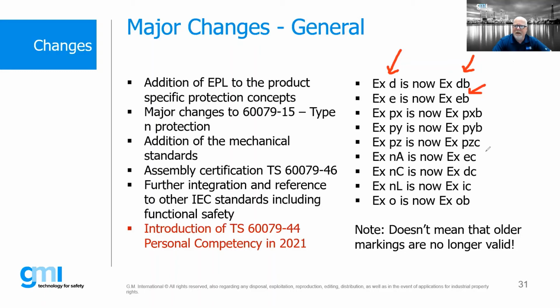Notice some of these N standards - some that were referenced within the Dash 15 standard have now been pulled out and put into other standards. For example, Ex nA, a lesser form of increased safety, non-arcing, was in the Dash 15 standard, but that information has now been put into the Dash 7 standard, which is increased safety. Ex nC, enclosed break, a lesser form of flameproof, is now in the Dash 1 standard. Energy limitation, NL, has now gone into the intrinsic safety standard.